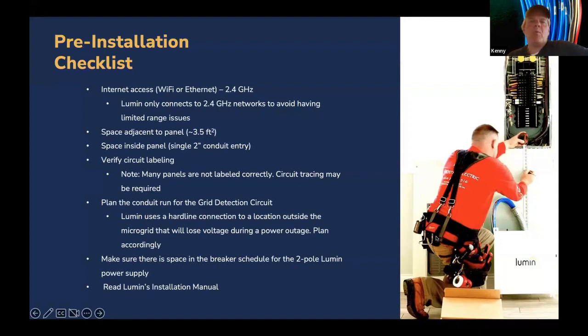At that point, it's also a good time to do your labeling check. Nine times out of 10, I'll go to a home and there's a labeling issue, so you might want to trace those circuits first. Then plan the conduit run for the grid detection circuit, which in my mind is probably the first thing we want to talk about with design, even before it gets onto the installer's truck, as it were. Lumin uses a hardline connection to a location outside of the microgrid that will lose voltage during a power outage, so plan accordingly.